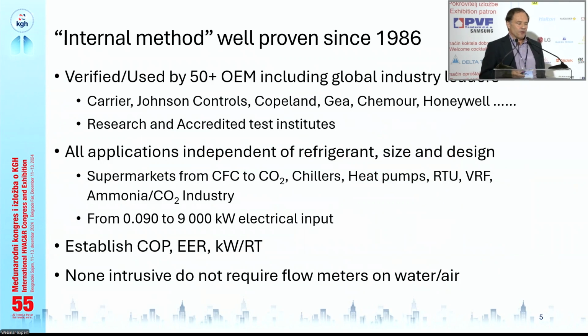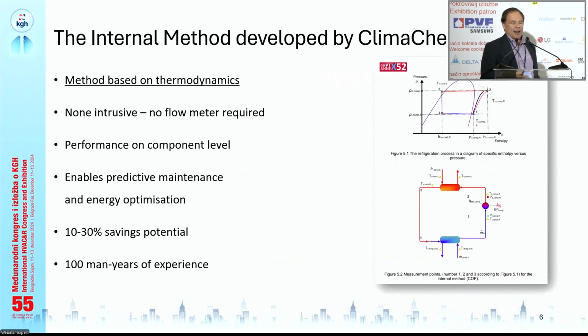It becomes quite a lot of mathematics and complexity when you have many different systems. I would say that we deal with basically everything today, from industrial, district heating, district cooling, down to small systems. But the beauty is that if we use our thermodynamics, we can calculate all the KPIs of a system in real time. It's all the conventional, of course, superheat, subcooling, and so on. But we can also calculate the energy efficiency on component level. We know the condenser efficiency, the evaporator efficiency, the cycle efficiency, and isentropic compressor efficiency. And then we also know the total efficiency of the system.